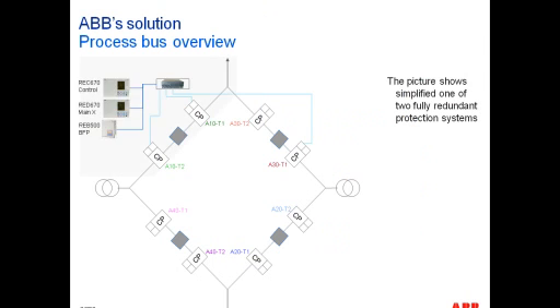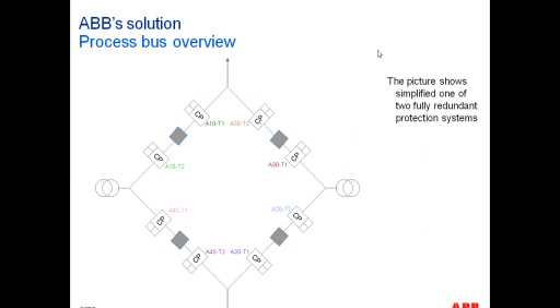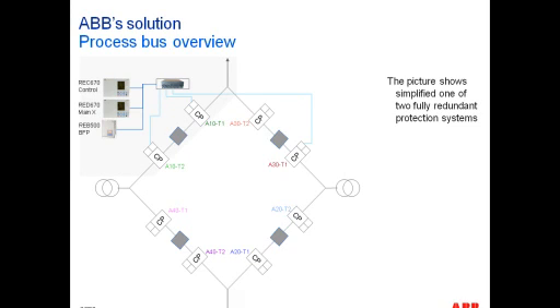So if we take a look at the one-line diagram of this substation, it's a ring bus where we have 2 lines and 2 transformers associated with it. We have 1, 2, 3, and 4 breakers associated with our ring bus, of course. And then these boxes right here that stand for CP are your current voltage sensors, which are essentially across the circuit breaker. So we end up with a total of 8 sensors that we will have information available for.